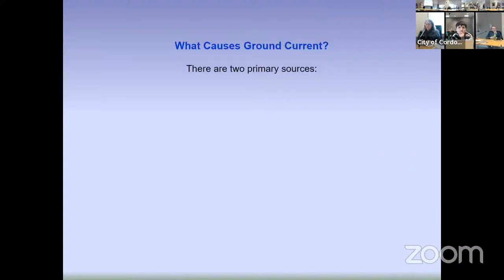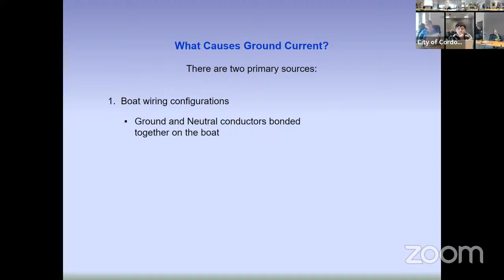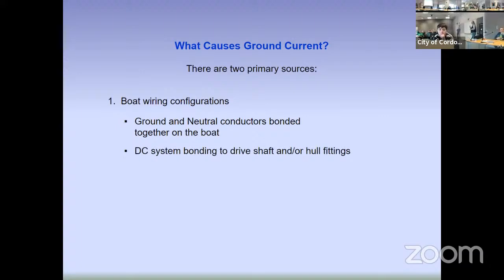Okay, so there are two primary sources that we have to be concerned with that will cause ground current. The first one is boat wiring configurations. Usually that's where our biggest problem is. I've got three different conditions here that are very typical. One is where the ground and the neutral conductors are bonded together on the boat. If that's the case, then it's very possible we'll get a ground current and it will trip the circuit breaker. The other is on some of the older boats, they used to be wired similar to a car, where the engine frame and the transmission and gearbox and all of that was used as the negative side. Well, with certain chargers, that would be a direct path into the water and caused a lot of problems.